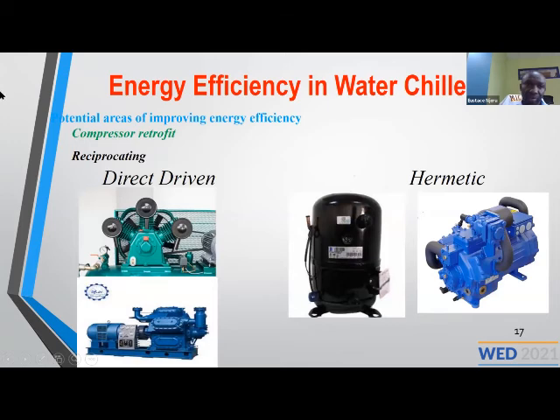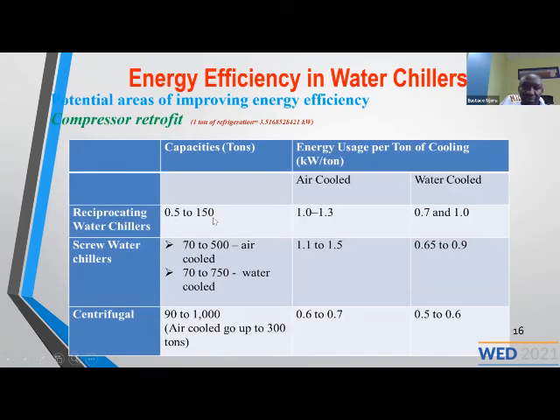So on the compressor retrofit, as you have said, if your system is below 150 tons of cooling load, and one ton of refrigeration is equivalent to around 3.52 kilowatts of thermal load being cooled, you don't have to use very big compressors. But once you go above 150 tons of cooling load, you need to employ screw compressors. And if you go above about 750, employ centrifugal compressors. So when you check your load and find that it is within this range, screw compressors are more efficient. For very small units like outdoor air conditioners, reciprocating compressors are better used.